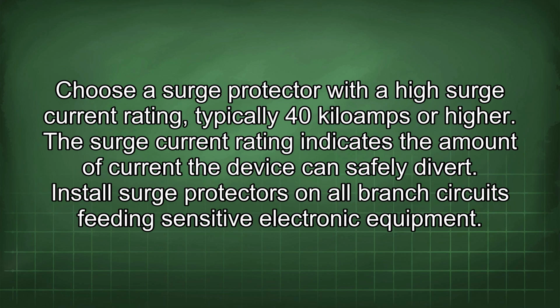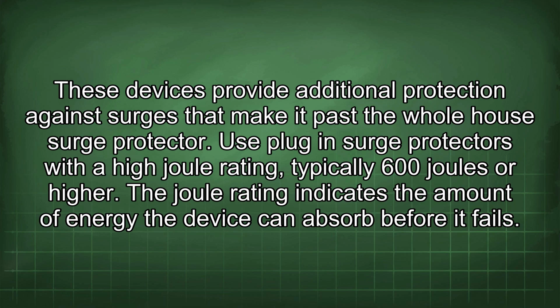Choose a surge protector with a high surge current rating, typically 40 kA or higher. The surge current rating indicates the amount of current the device can safely divert. Install surge protectors on all branch circuits feeding sensitive electronic equipment. These devices provide additional protection against surges that make it past the whole house surge protector.